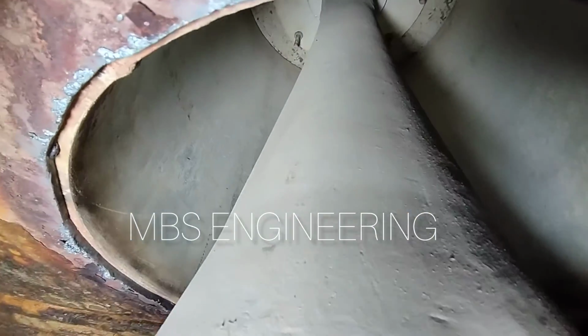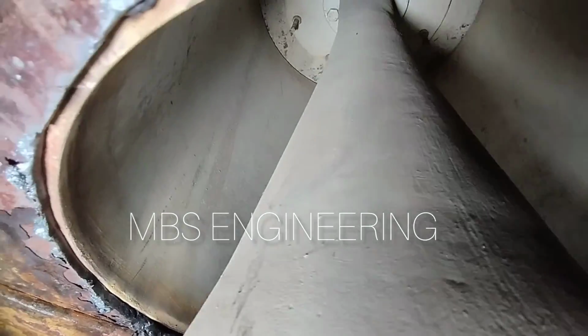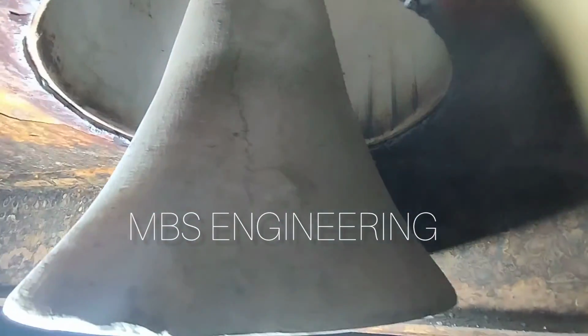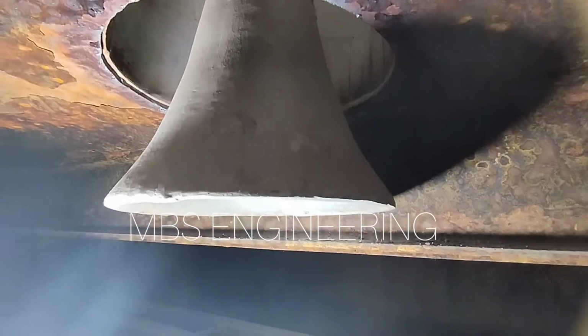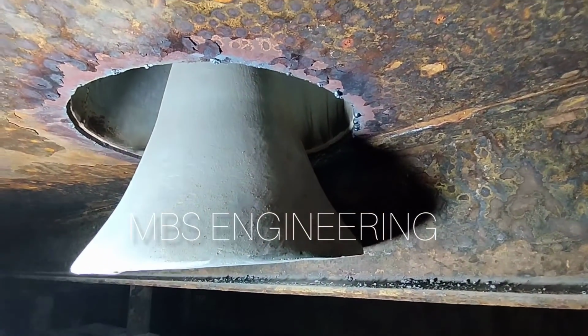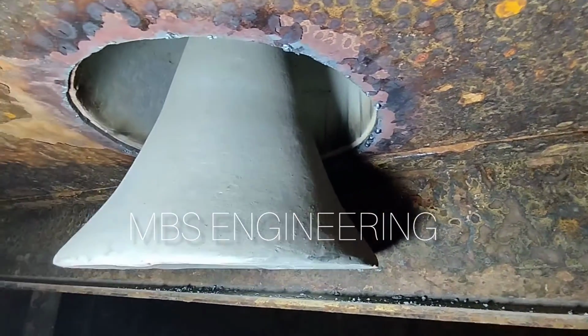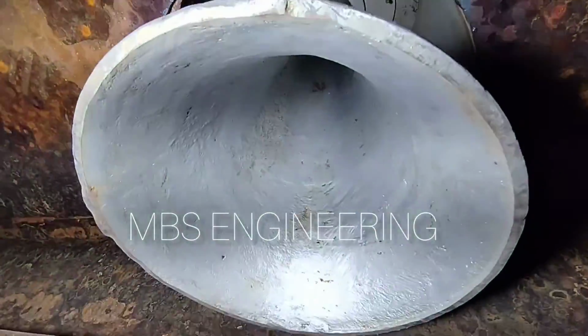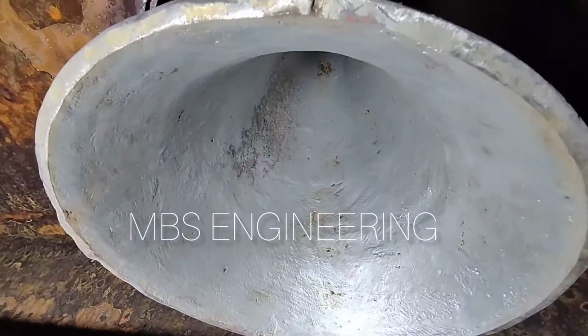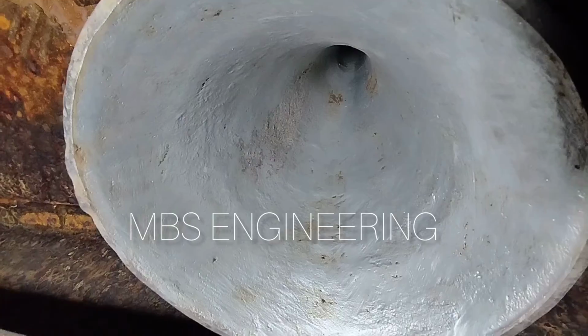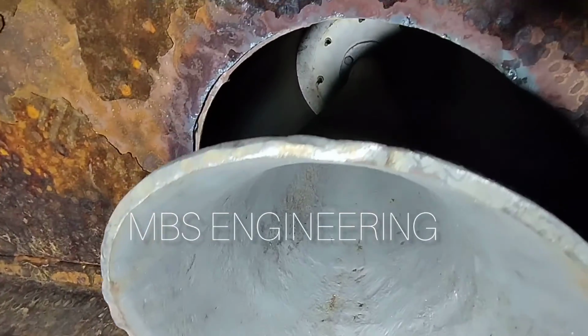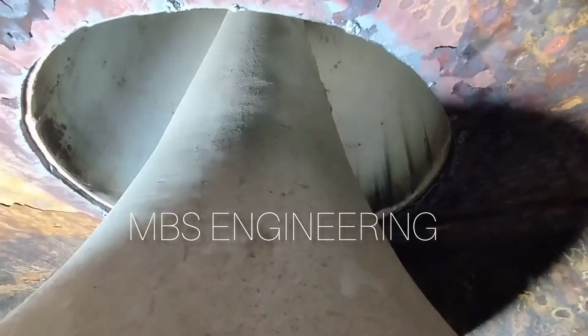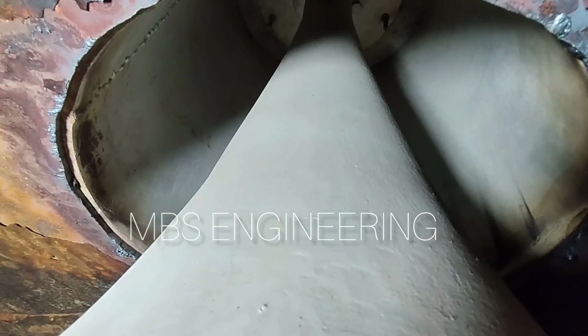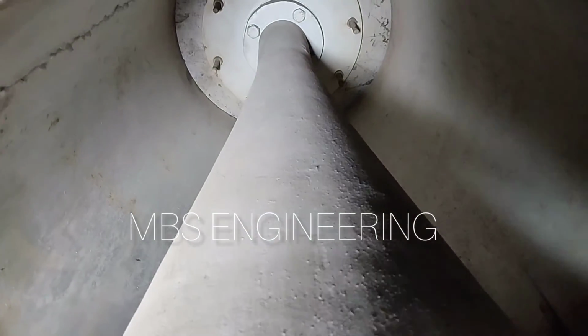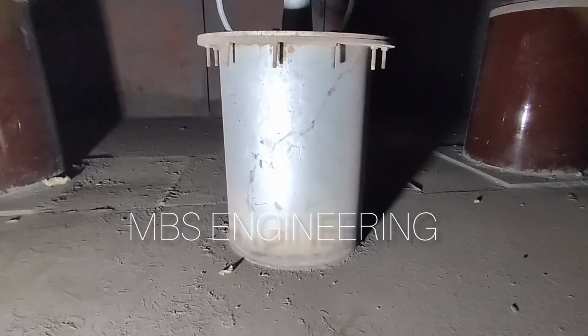The sound emitter sonic horn is powered by compressed air pressure of 5 to 7 kilograms per centimeter square. It produces a sound wave of 140 to 150 decibels. The sonic horn activates for 10 to 20 seconds after every 10 minutes to 30 minutes automatically depending upon the dust load on the surfaces of the equipment. The sonic horn is increasing the efficiency and output capacity of the boiler and ESP.